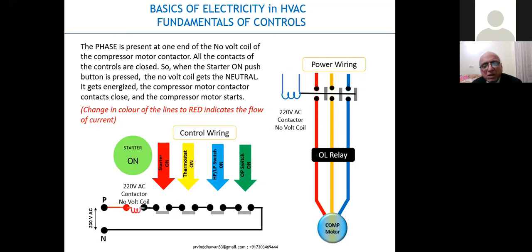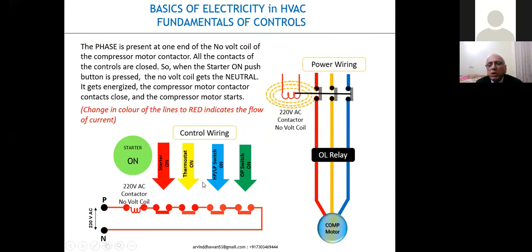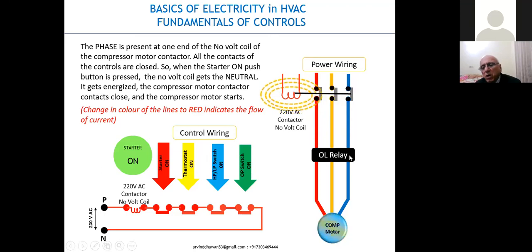Then a little bit about controls — how these things work. You can see the current flowing and all the contacts of all the controls are in series with the no-volt coil of the contactor. If the current flows through all the contacts, then the no-volt coil gets the supply. It creates a magnetic field, pulls the plunger, and all the main contacts come into circuit, completing the power circuit to the compressor motor.